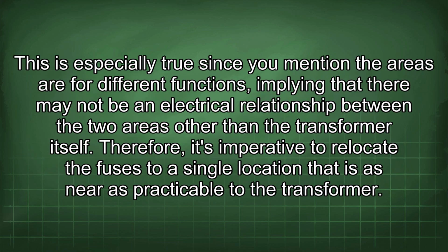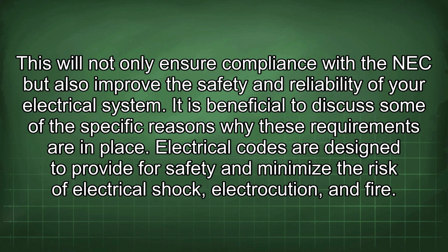This is especially true since you mentioned the areas are for different functions, implying that there may not be an electrical relationship between the two areas other than the transformer itself. Therefore, it's imperative to relocate the fuses to a single location that is as near as practicable to the transformer. This will not only ensure compliance with the NEC but also improve the safety and reliability of your electrical system.